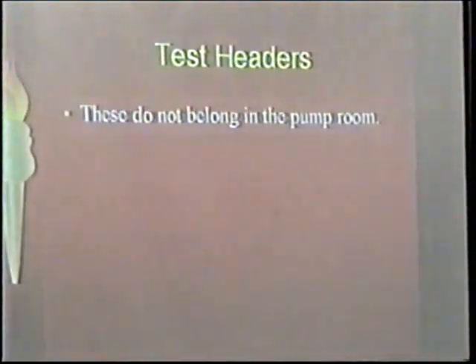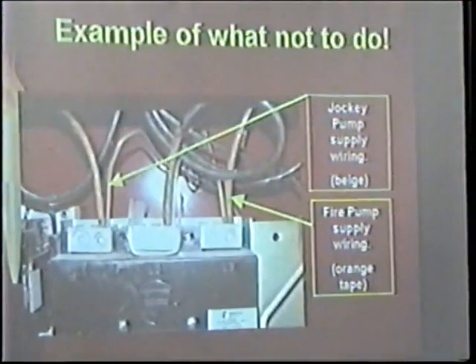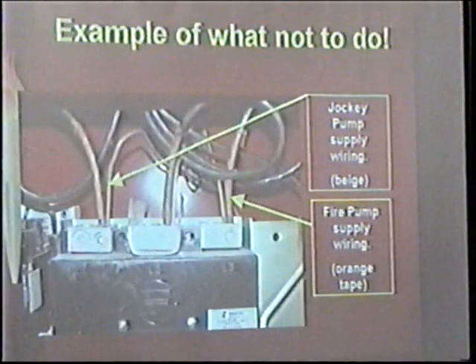Test headers. It seems to me a couple times in the last year I've run into a pump somewhere that had test headers still in the pump room. Code book says it's not supposed to be there. So, it's dangerous, because if you start running the hoses out through the door, and something happens in the pump room, you've got to be running across those hoses. It's just not safe. Here's the old problem. This is an old photo, and I admit it. But this is where they've tapped the jockey pump wires off the incoming power from the utility. And I can't believe they're saving that much money, but that's the way they seem to do it. And we still find, probably a couple of years, that contractors have done that one.